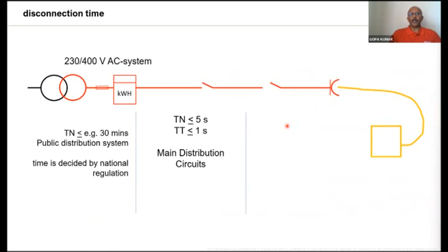One of the subjects which is very important is the disconnection time. Say, for example, in case of a fault of negligible impedance, as I told you, if you are able to disconnect the faulty circuit within 3 seconds, the chance of fire is almost zero. The electrical items are not supposed to ignite fire if the fault is cleared within 3 seconds. Now, if we look at the wiring standard IS 732, these are the maximum allowed disconnection times in case of a fault of negligible impedance. It is not even 0.3 seconds. It is just 0.4 seconds.